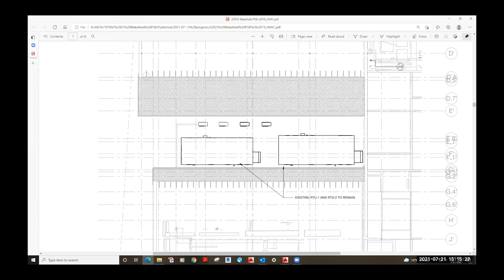So this testing and balancing would confirm that unit still performs at a 10,000 CFM capacity, or is performing at some level where that unit might be operating at 10,000 CFM capacity at, say, 90%, with some additional capacity where it's not operating at 100%. So we would test: can it provide 10,000 CFM, and what is it actually providing? And if it's providing something less than that, maybe we don't need to replace it.